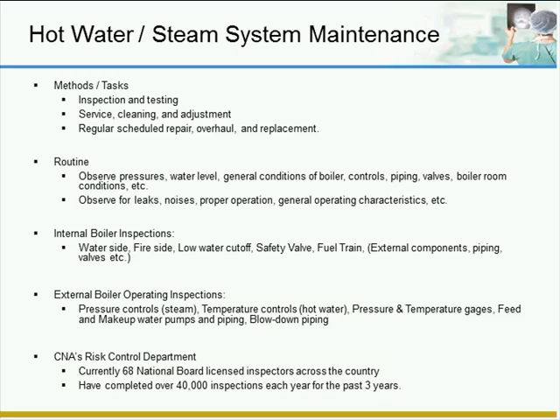On the routine side of things, you have the observation. You want to check temperatures and pressures, water levels, just the overall condition of the boilers. You want to make sure the piping is safe, there are no steam leaks, and the safeties and controls look like they're in proper working condition. You'll have your routine checks as well as routine duties. Blow down boilers. The low water cutoff needs to be blown down on a routine basis. Safety valves should be tested on a routine basis.